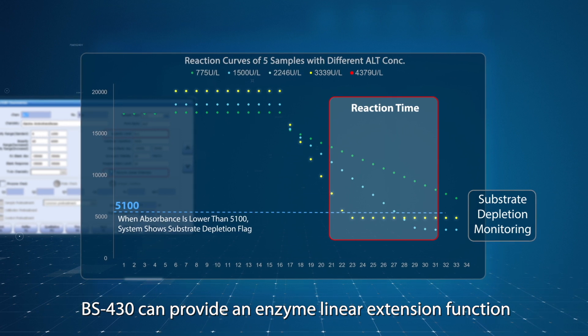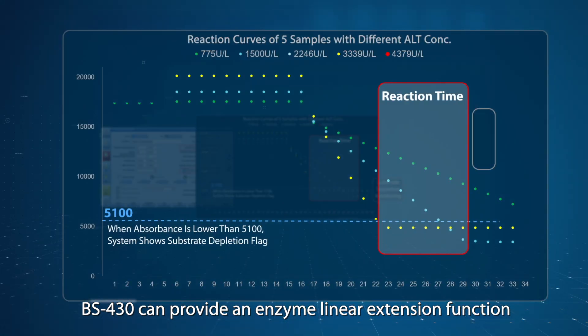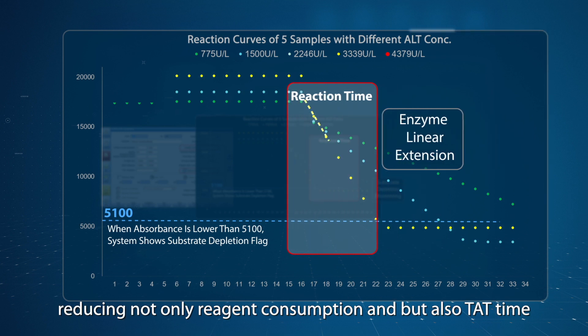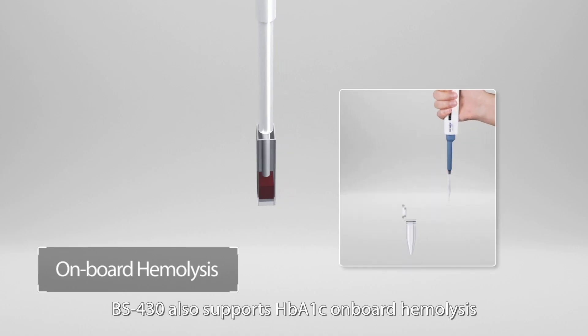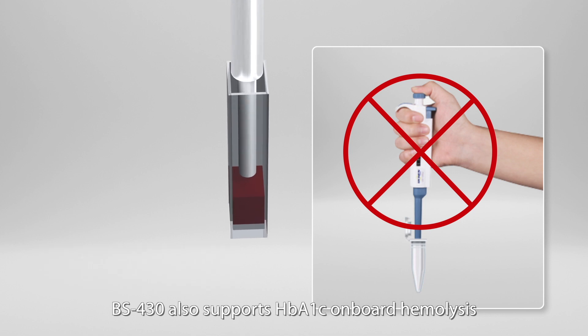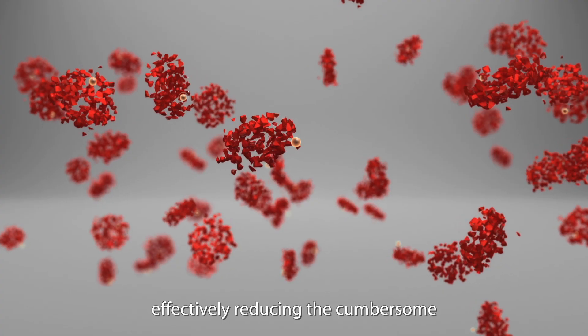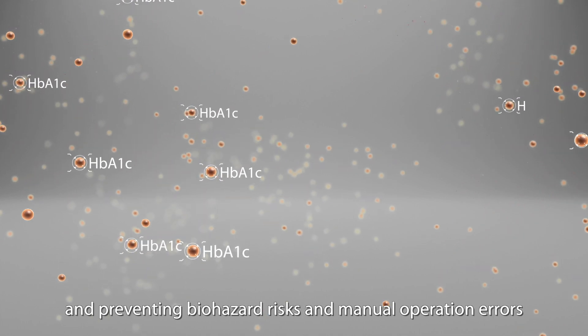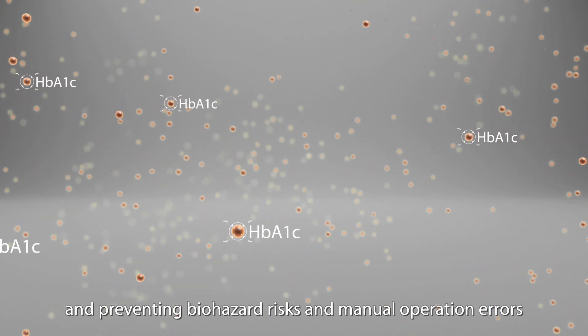Moreover, BS430 can provide an enzyme linear extension function, which delivers reliable results without dilution and rerun, reducing not only reagent consumption, but also TAT time. BS430 also supports HBA1C onboard hemolysis, effectively reducing the cumbersome procedures of manual preparation of hemolysates and preventing biohazard risks and manual operation errors.